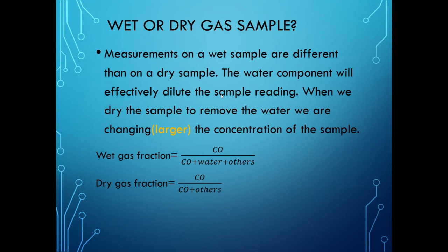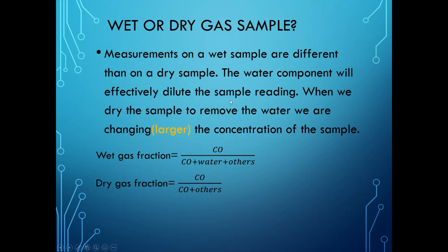Measurements on a wet sample differ from those on a dry sample — the water component effectively dilutes the sample reading. If you expect to measure one cubic centimeter out of 100 cubic centimeters of gas, but 40 cubic centimeters are actually liquid, you're really measuring one cubic centimeter out of 60, giving a false higher concentration. That's what this section addresses — having contaminants in your sample affects the actual measured concentration.